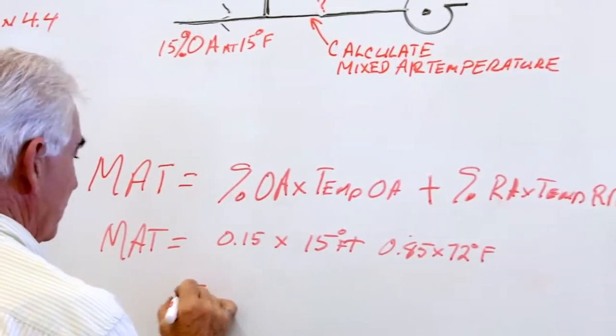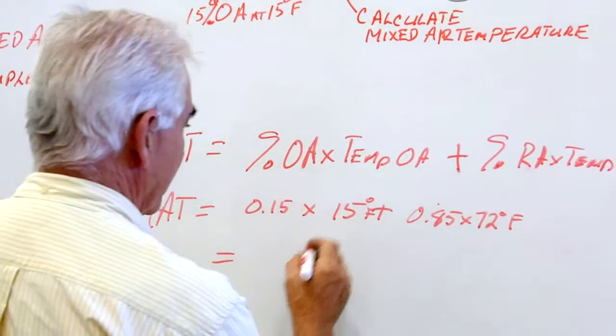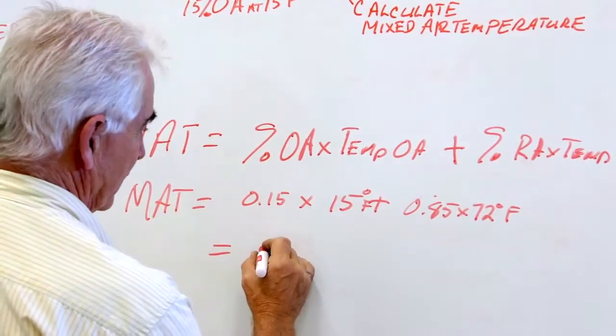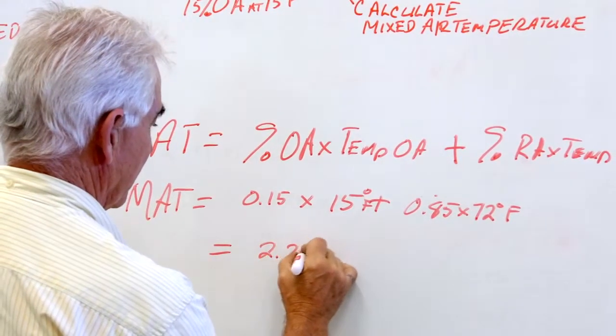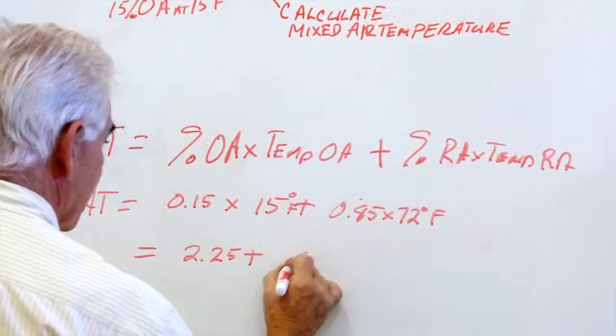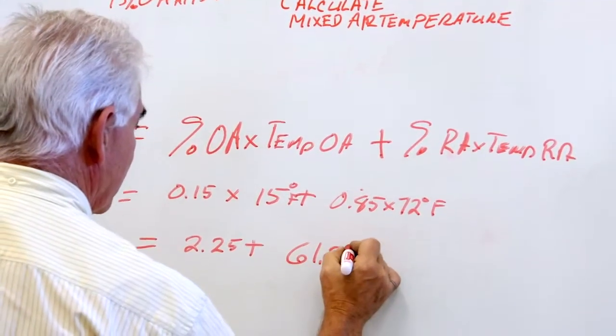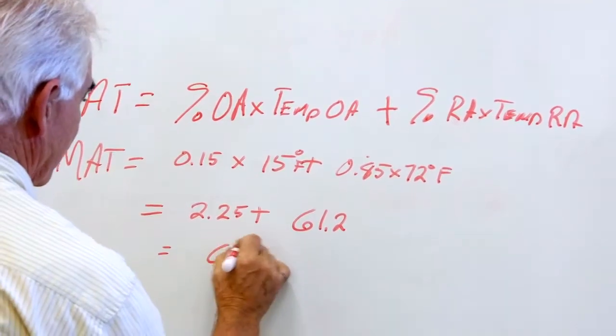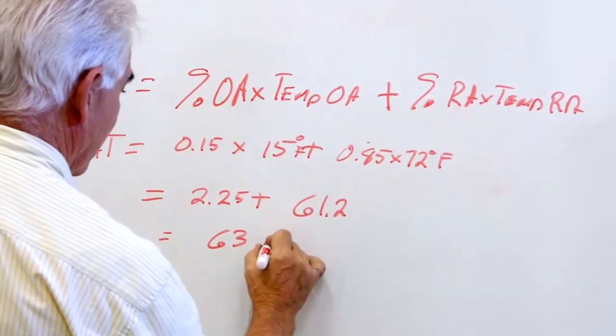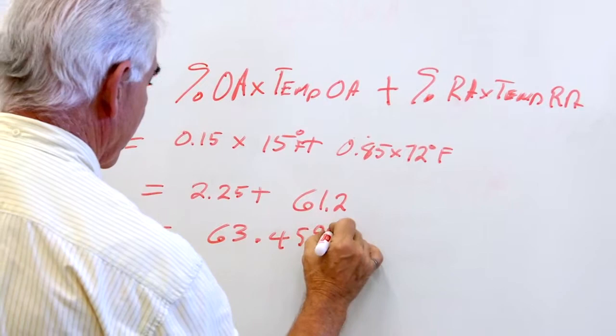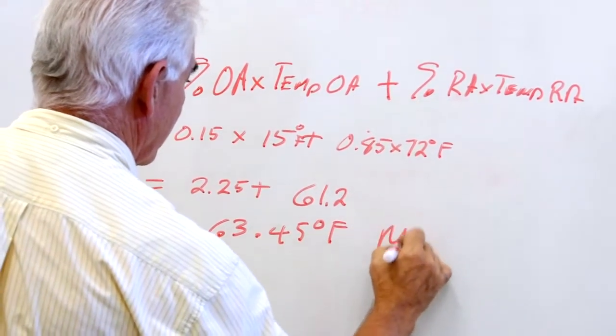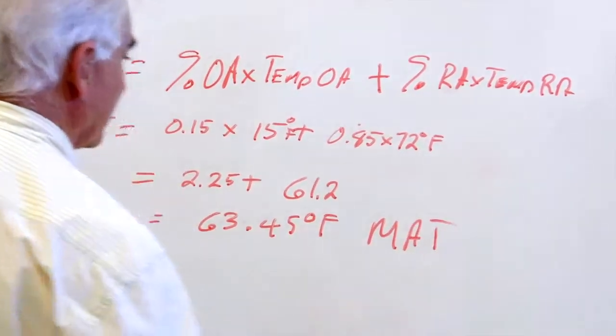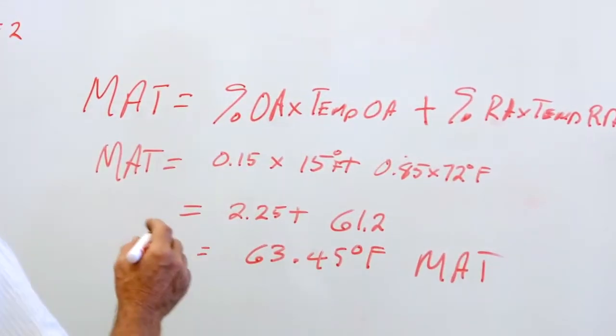And when we work that out, we get 15 times that. That's 2.25 plus 61.2 and that's equal to 63.45 degrees Fahrenheit mixed air temperature.